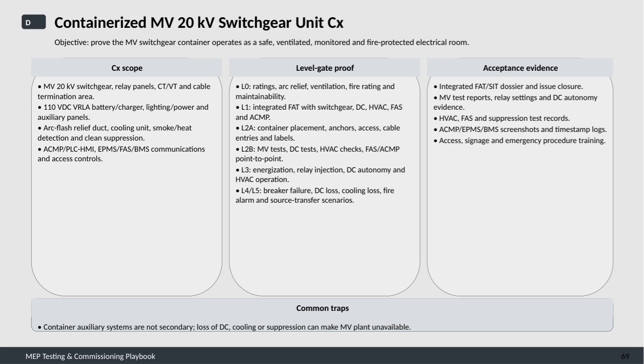Finally, Levels 4 and 5 simulate failure scenarios, such as breaker failure, DC power loss, cooling loss, fire alarm activation, and source transfer situations. For acceptance evidence, this process generates several key documents and records: a comprehensive integrated FAT and site integration test dossier with issue closure, detailed medium voltage test reports, relay settings, and evidence of DC autonomy.